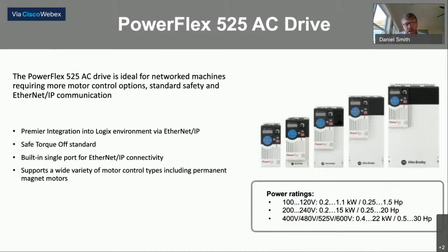So our 525 drives, you can see it looks identical to the 523 like we spoke about earlier. If the picture wasn't a little grainy, you'd see it just says 525 on the front. The biggest difference between the 523 and the 525 is the 525 has embedded Ethernet and also embedded safe torque off. So right out of the box, it is able to be put on an Ethernet network, integrate with a Logix environment, and then wire in hardwired safety controls.